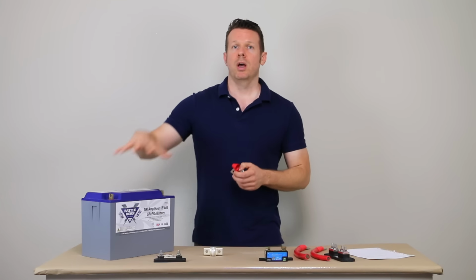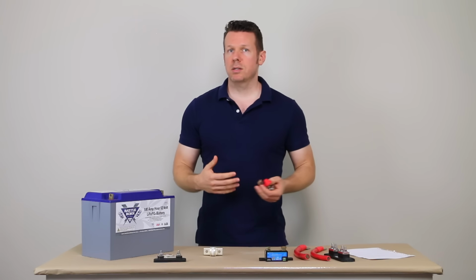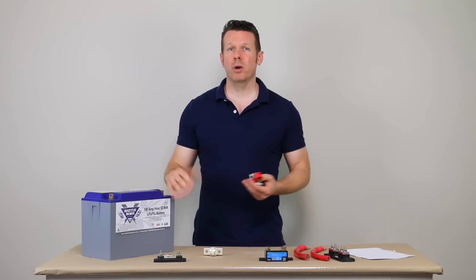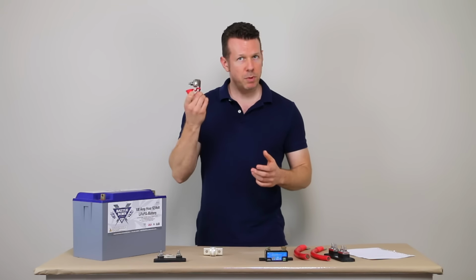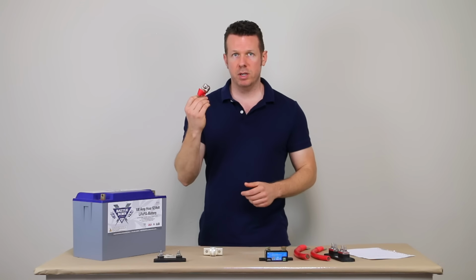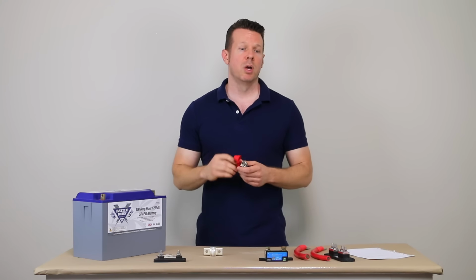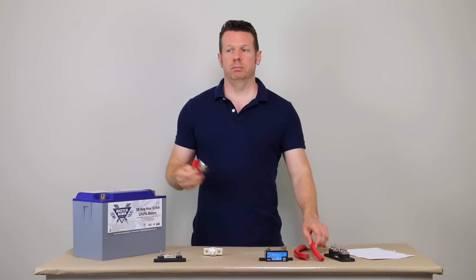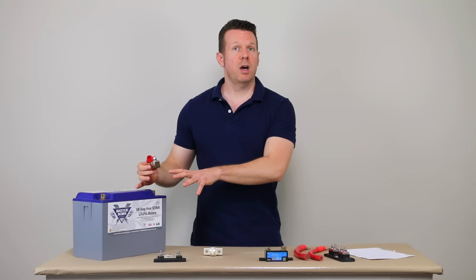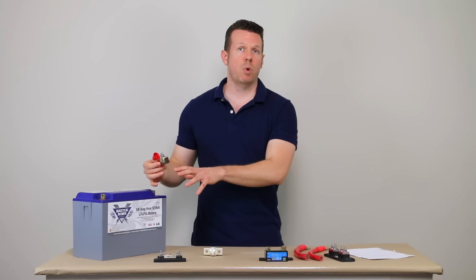So if you have a very big battery bank, and in that case I would put a 400 amp fuse, you're not going to be able to use the MRBF, but it is definitely usable in the rest of the system. Or if 300 amps is enough, at 12 volts, that's 3,600 watts.